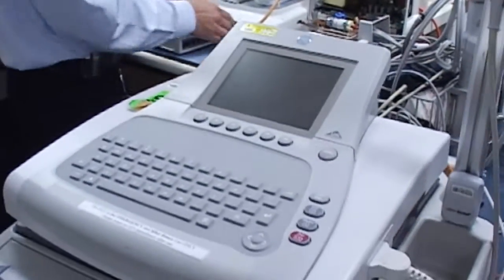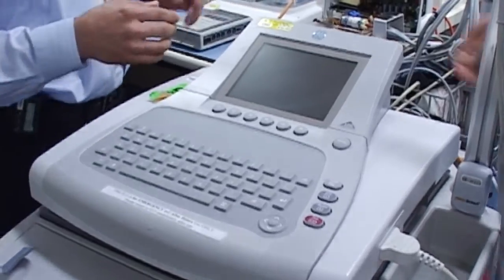You want to have a look at this one? It's come down from a ward saying that it's not reading correctly. It's a pretty vague description, but what we're going to do now is just put essentially a patient simulator on it, which is just one of these.